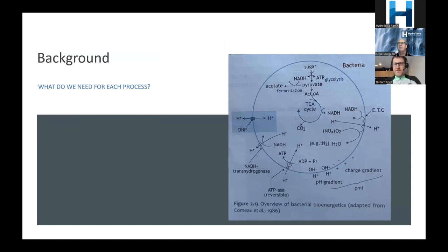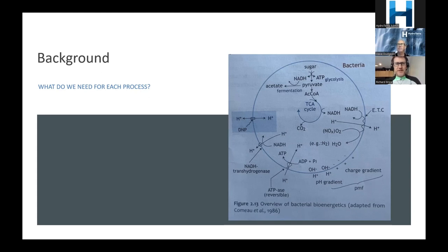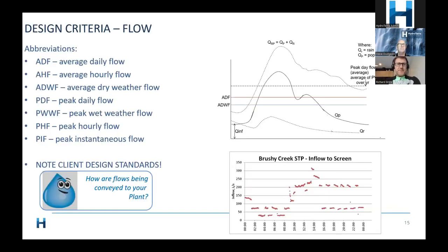What do we need for each process? I like this pathway diagram around phosphorus removal and bug uptake. We need to understand: A — our effect on the environment; B — the performance of a treatment plant asset; C — what treatment plant we need; and D — how to make the process we have work better, including from a process emissions perspective. Fundamentally, without understanding what flow we have coming into a plant, we struggle to do anything. It's really important to audit what's coming into a process — not just installation of metering equipment but also data transfers to ensure information is reasonable and accurate.